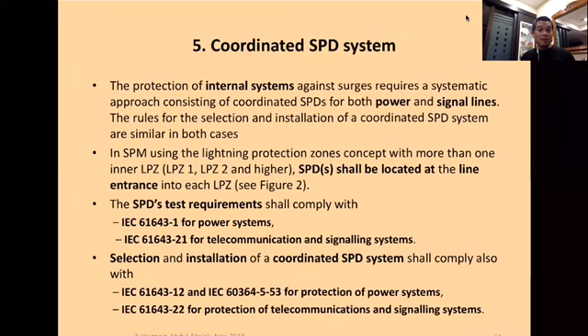Now, we have already described the coordinated SPD system. This is actually zoning or minimizing surges using SPDs. So to repeat, number 5 is SPD. It can be for the power line as well as for signal line. So based on whether it's for power or signal, which is lower voltage, we have different standards mentioned here. These are for the power lines; we should use these SPDs and standards to test for the power system.